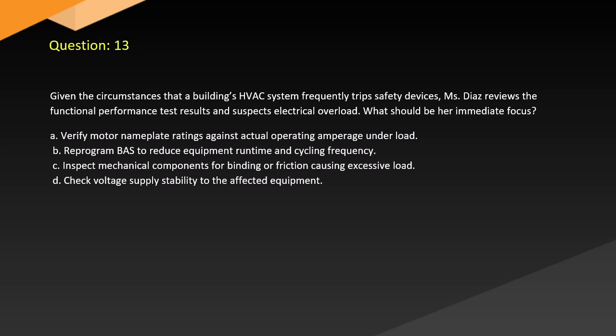Question 13. Given the circumstances that a building's HVAC system frequently trips safety devices, Ms. Diaz reviews the functional performance test results and suspects electrical overload. What should be her immediate focus? A. Verify motor nameplate ratings against actual operating amperage under load. B. Reprogram BAS to reduce equipment runtime and cycling frequency. C. Inspect mechanical components for binding or friction causing excessive load. D. Check voltage supply stability to the affected equipment.